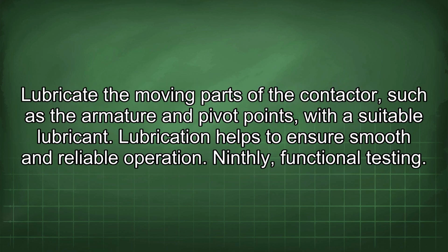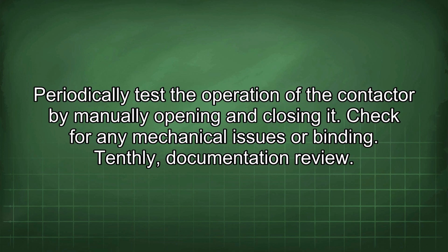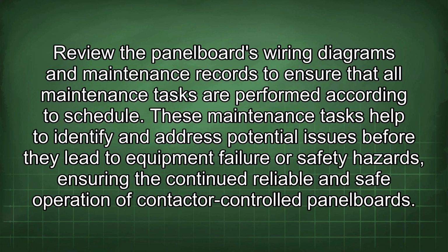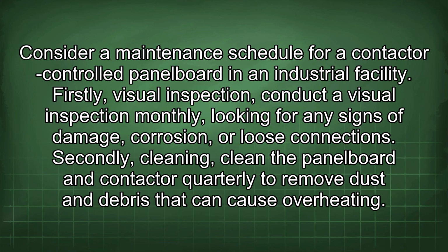Eighthly, lubrication. Lubricate the moving parts of the contactor, such as the armature and pivot points, with a suitable lubricant. Lubrication helps to ensure smooth and reliable operation. Ninthly, functional testing. Periodically test the operation of the contactor by manually opening and closing it. Check for any mechanical issues or binding. Tenthly, documentation review. Review the panel board's wiring diagrams and maintenance records to ensure that all maintenance tasks are performed according to schedule. These maintenance tasks help to identify and address potential issues before they lead to equipment failure or safety hazards, ensuring the continued reliable and safe operation of contactor-controlled panel boards. Consider a maintenance schedule for a contactor-controlled panel board in an industrial facility.